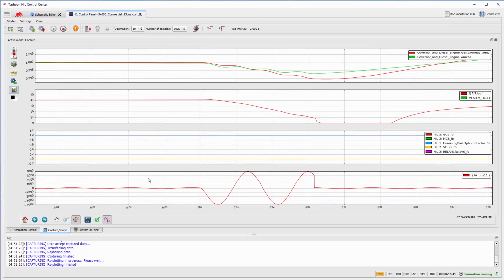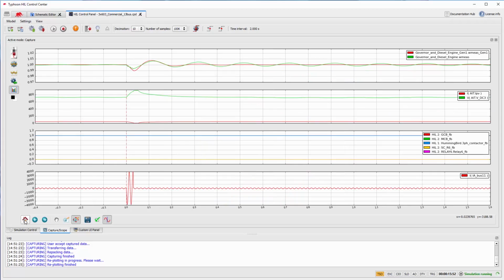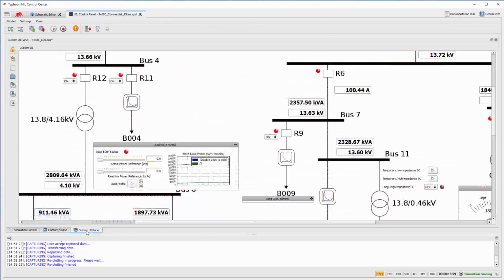As we can see, the Hummingbird did not disconnect with this fault. The AIT inverter stopped operating for a few milliseconds and went back to nominal operation. The gensets had similar behavior to the first short circuit analyzed. Let us once again bring our microgrid back to nominal operation.